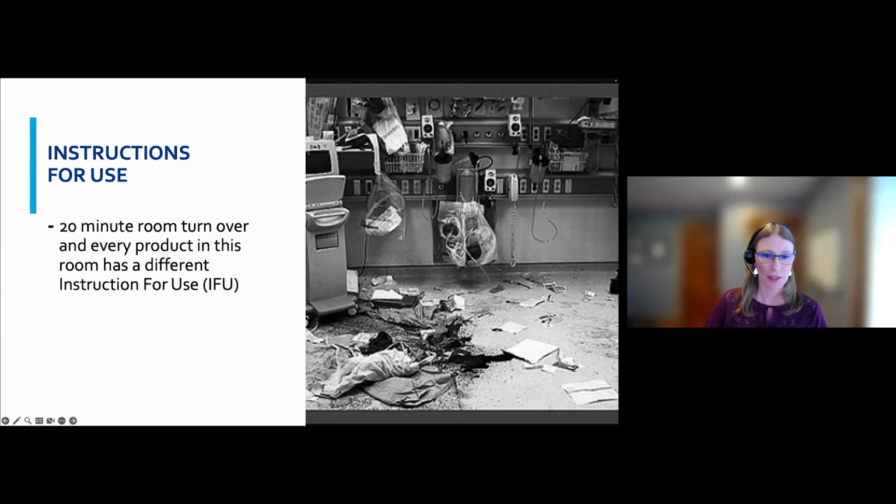Yeah, and I definitely will go into that in more detail, but certainly sometimes when the IFU says what the compatible product is, it's not a product that is suitable for healthcare. So for example, there was a common piece of equipment that's used to cool patients in cardiac surgery. And the product that was recommended to use based on the compatibility was Pine Sol. If you think about it, Pine Sol is something certainly that we could use in our homes, you know, to clean and disinfect our surfaces.